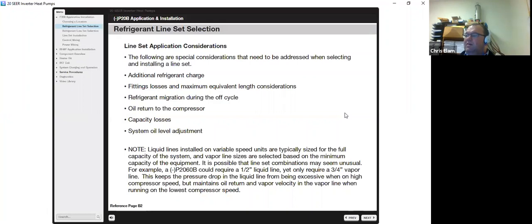It is possible that line set combinations may seem unusual. I saw this with a 2-ton, I believe it was, and the dealer was questioning that, but in fact, that's what it called for. For example, a RP2060B could require a 1/2 inch liquid line, yet only require a 3/4 inch vapor line. This keeps the pressure drop in the liquid from being excessive when on high compressor speed, but maintains proper oil return and vapor velocity in the vapor line when it's running at the low speed.